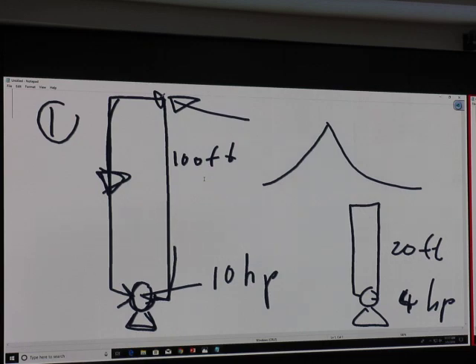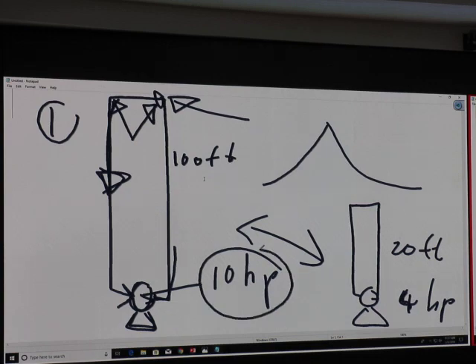So this means when I design the pump, I have to make sure that it can reach the steady state case. Or this means it can pump until it reaches that point. When it goes down, it gains pressure, but when it goes up, it loses pressure. When the pipeline is small, it loses pressure to the friction. Good. So both cases cannot use the same pump. And the actual horsepower will be more than 10 horsepower if 10 horsepower just account for the friction. Because hydrostatic head term also needs to be accounted for.